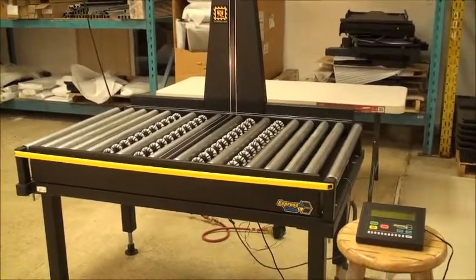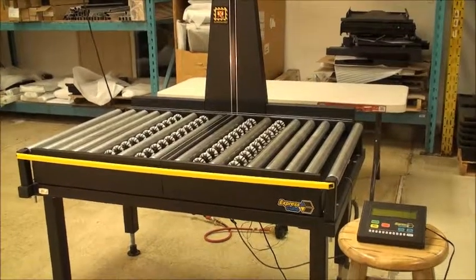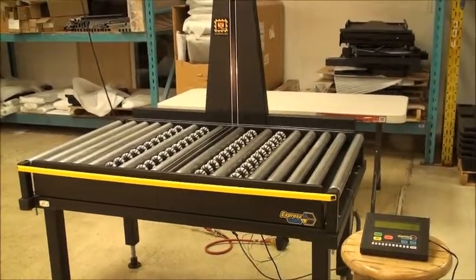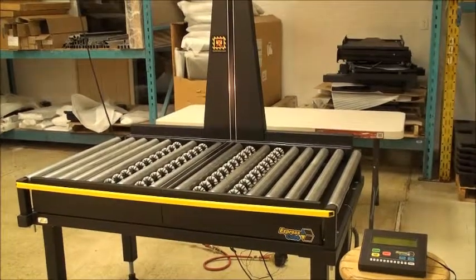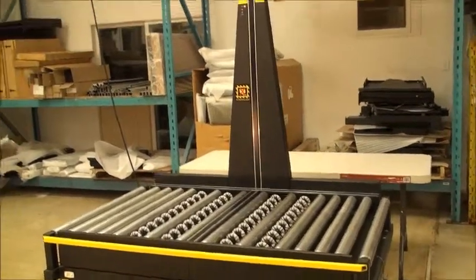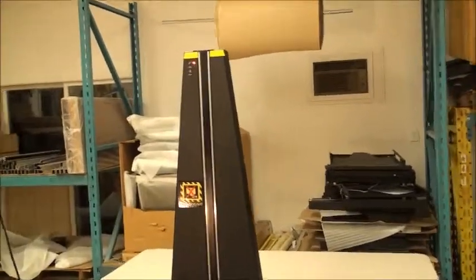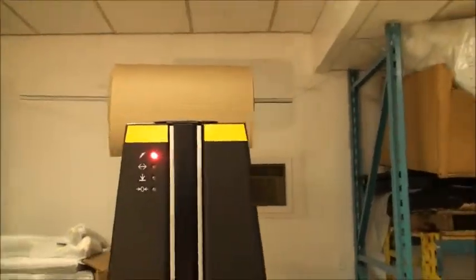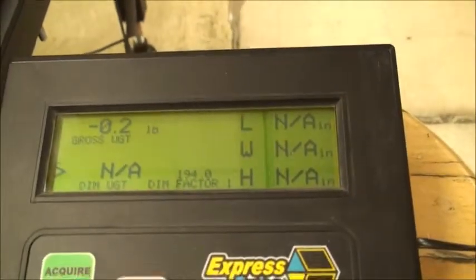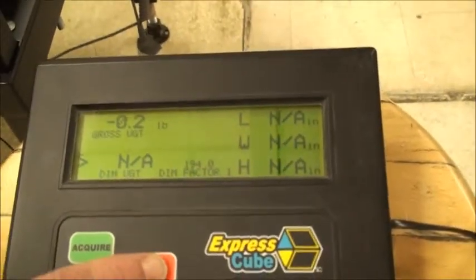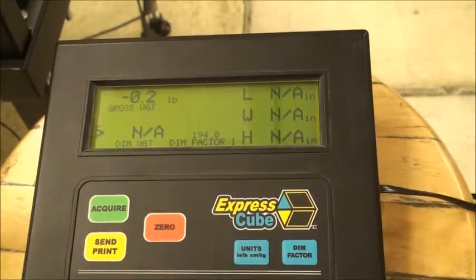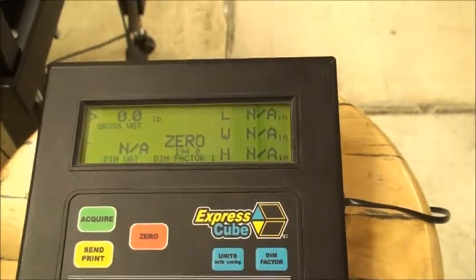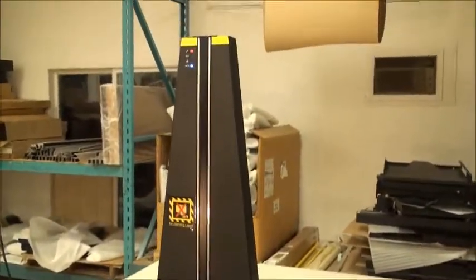First, we've intentionally put an offset in. When we look at the empty 480 platform, we notice only the red light is on, where we know we should have a red and a blue. If we verify that with the LCD controller, we'll see it's not showing 0, it's actually showing a weight. So the first thing we can do is press the 0 button, and now with the empty table, the system is ready to go.